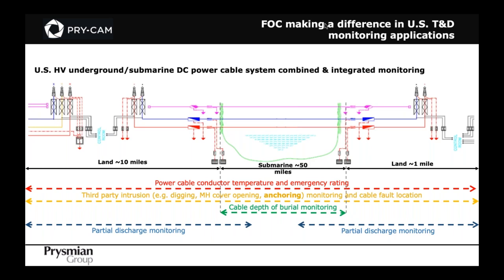The solution implemented and installed is an end-to-end DTS RTTR solution for power cable conductor temperature and emergency rating purposes, as well as depth of burial monitoring of the 50-mile submarine section.